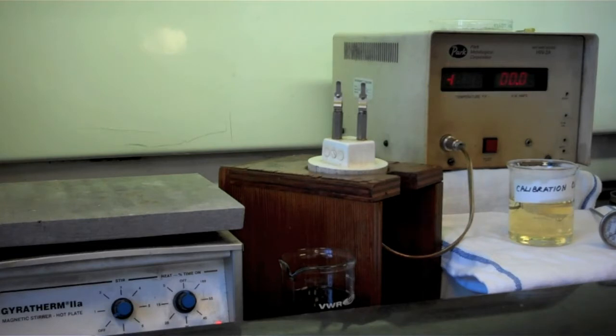In the hot wire testing, the wire is heated from room temperature to a higher temperature by passing an increasing electric current through it. The heat generated in the wire is continuously taken away by the oil until a point is reached when the generated heat is more than what's taken away by the oil. At that point, the wire fuses, and that's what we call the hot wire reading.